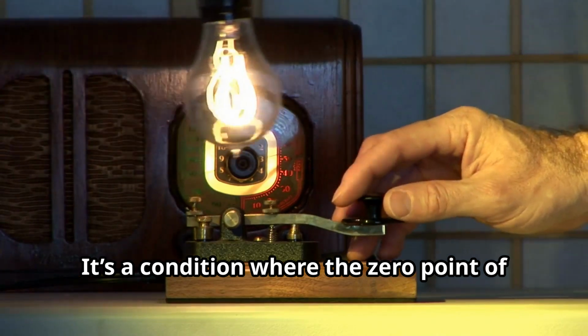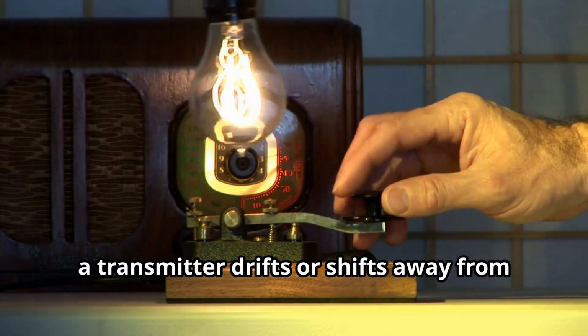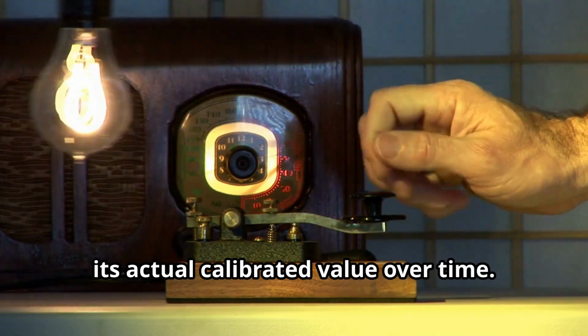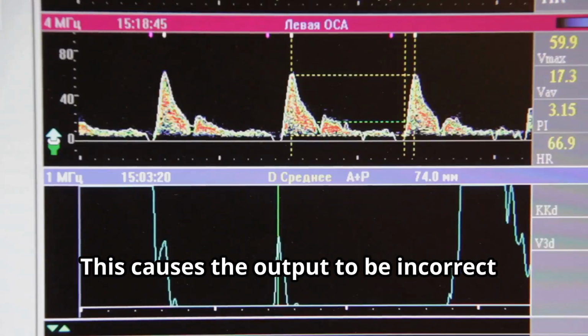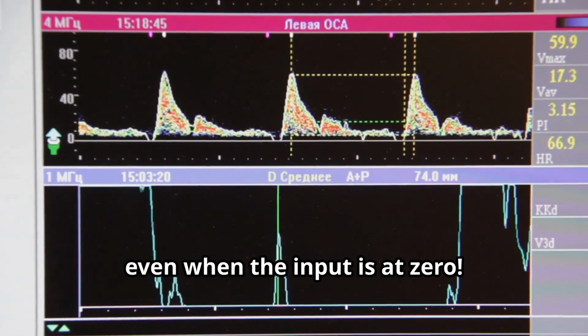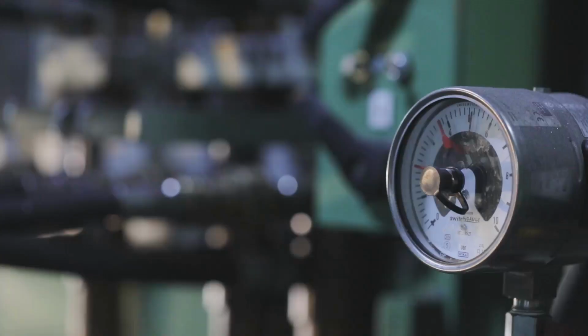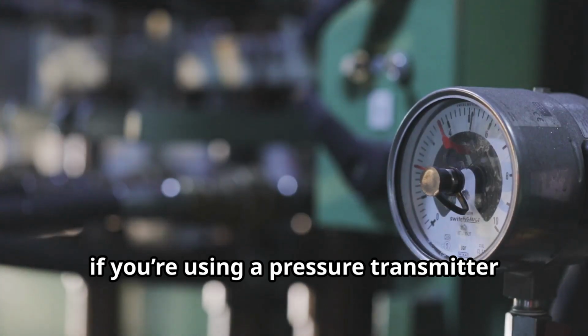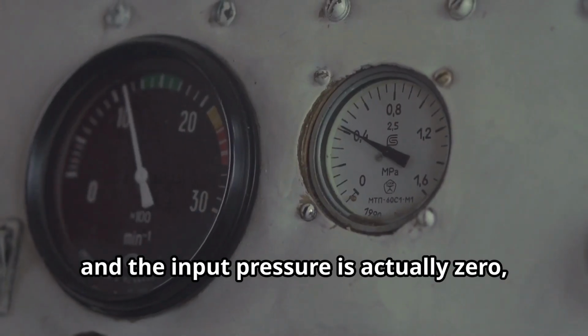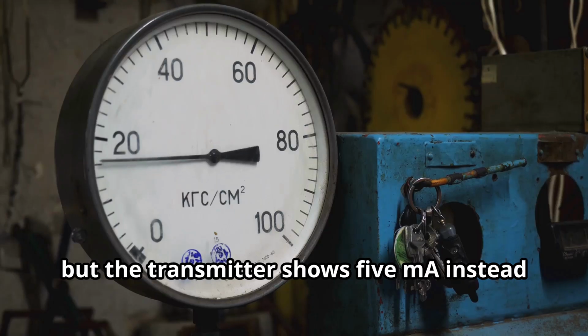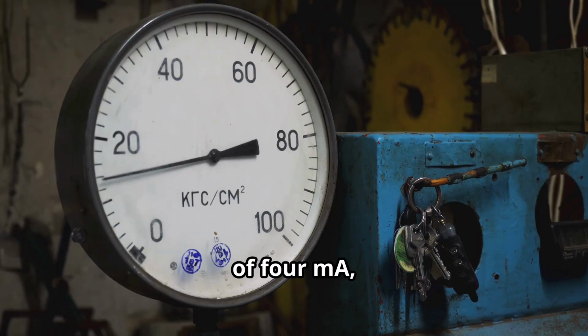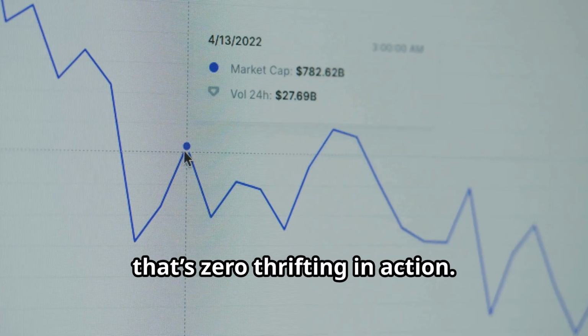It's a condition where the 0 point of a transmitter drifts or shifts away from its actual calibrated value over time. This causes the output to be incorrect, even when the input is at 0. For example, if you're using a pressure transmitter and the input pressure is actually 0, but the transmitter shows 5 mA instead of 4 mA, that's zero drifting in action.